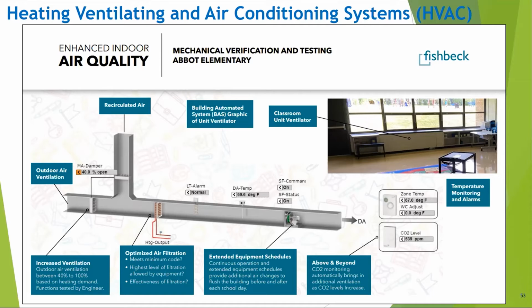And in the cases where we have CO2 monitoring, that's a device that measures the amount of carbon dioxide in a space. For whatever reason, it's easier to monitor CO2 than to measure oxygen levels, but it's basically an indicator of how many people are in the space. When your CO2 levels rise, that means that there are lots of people in the space, and so it would kick on more ventilation as that CO2 sensor indicates. So that's a basic sort of unit ventilator ventilation system.